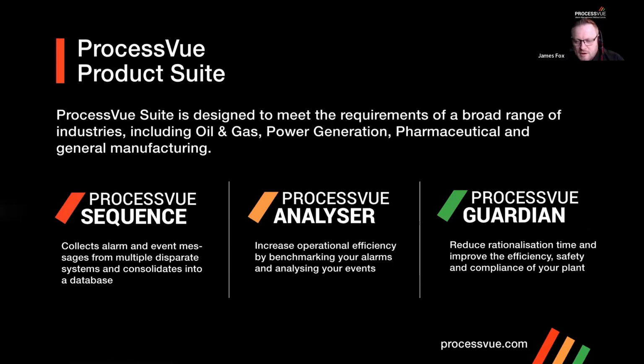We've then got the ProcessVue Guardian, which is our master alarm database application. It provides a management of change workflow, which ensures any changes to alarm settings have to be approved before they can be deployed. It includes a productivity toolset, which enables more efficient alarm rationalization and documentation activities with features such as copy one alarm to many and the ability to batch edit large numbers of alarms.